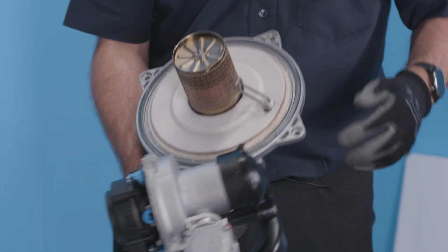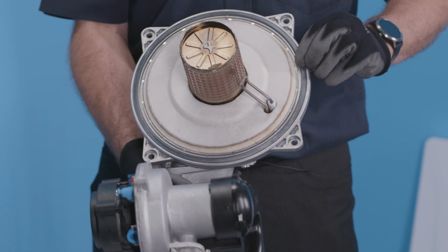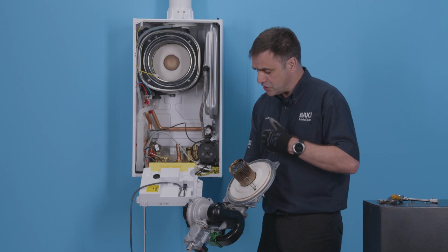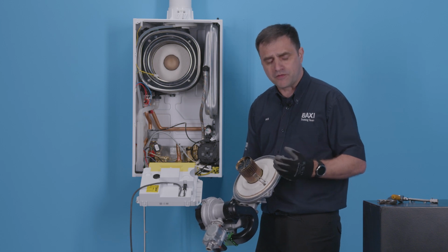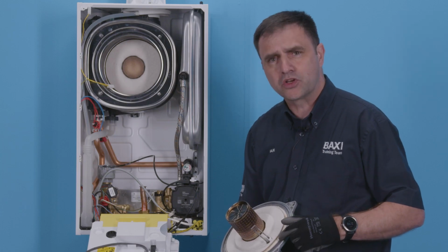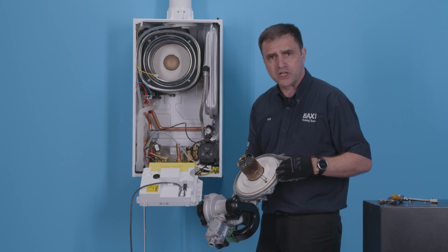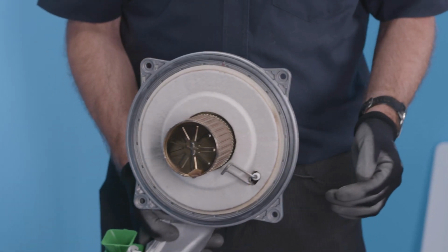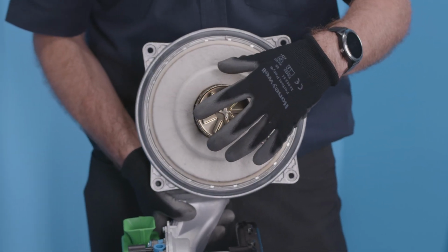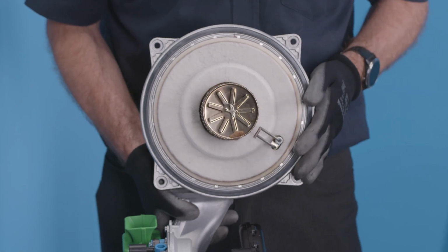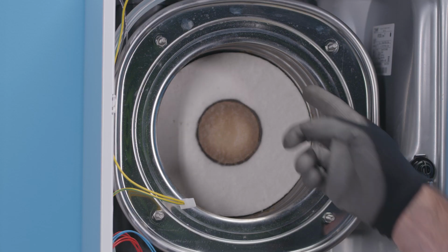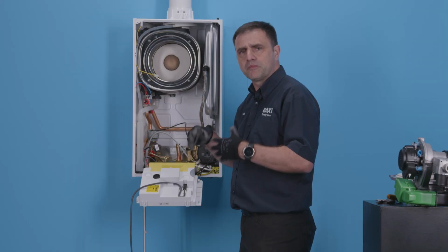What we can see on here, we've got our burner seal. This one's nice and springy, and that's what I'm looking for. You don't have to replace the burner seal on every service. All you have to do is make sure it's in good condition, and if it is, reuse it. You can see it's a serrated edge burner holding the flame closer to the burner, giving you more heat per square inch.